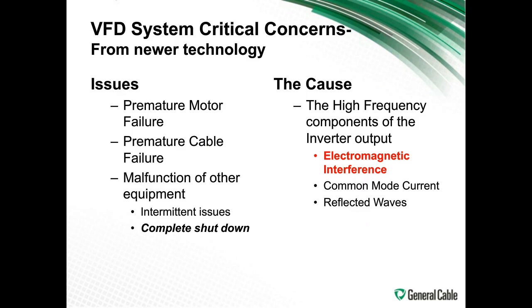So the critical concerns, again, from this newer technology, as I explained earlier, are premature motor failures, premature cable failures, and possible complete shutdown. The high-frequency components of the inverter output create the electromagnetic interference, common mode current, and the reflected wave. These are the evil that they create, and this is what we have to take care of.